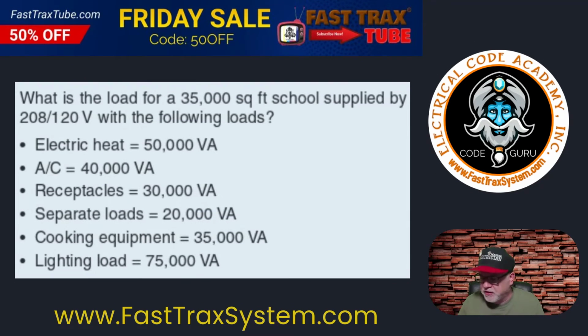All right, so let's look at this example. We've got our calculator, and we can work this out. What is the load? We're going to try to calculate what our VA is. It says, what is the load for a 35,000 square foot school supplied by a 208/120 volt service with the following loads? We've got heating, which is 50,000 VA.